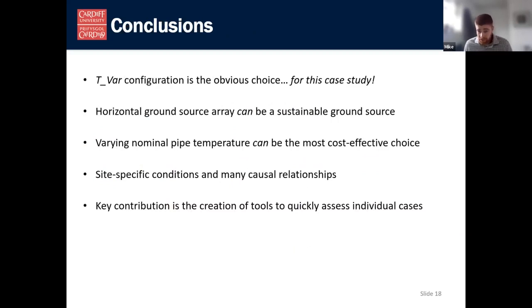But what we'd like the takeaway point to be is not that this is exactly how these networks should be designed. The horizontal ground source array can be a sustainable ground source if you have sufficient land and suitable soil conditions. Varying nominal pipe temperature can be the most cost-effective choice, but we could have changed any number of parameters in the case study and got a different result. For example, if we had a different pipe topology with longer pipe lengths, or if there'd been better overlap between heating and cooling loads. But what we've hopefully shown is that we have these tools available to assess these networks on a case-by-case basis. And these methods are already published or are currently under review to be published, so they can be accessed in that way.